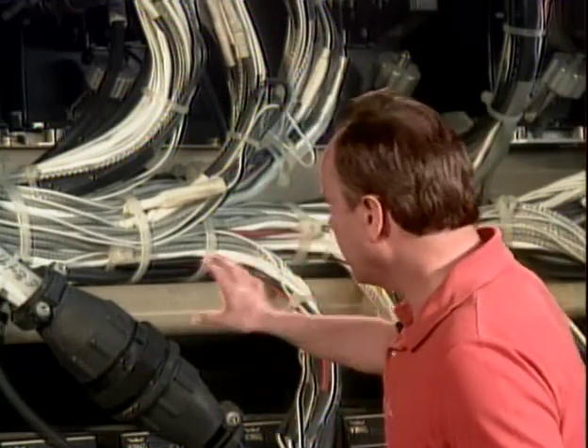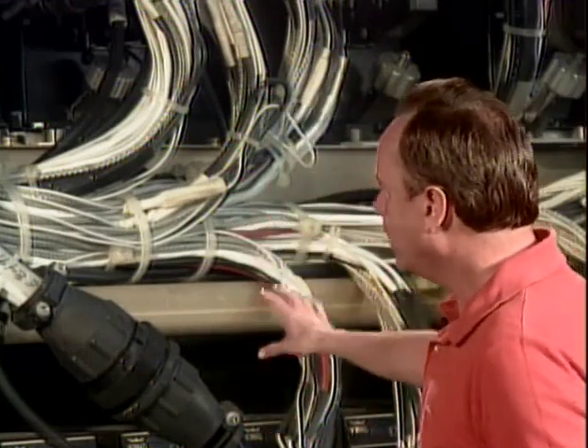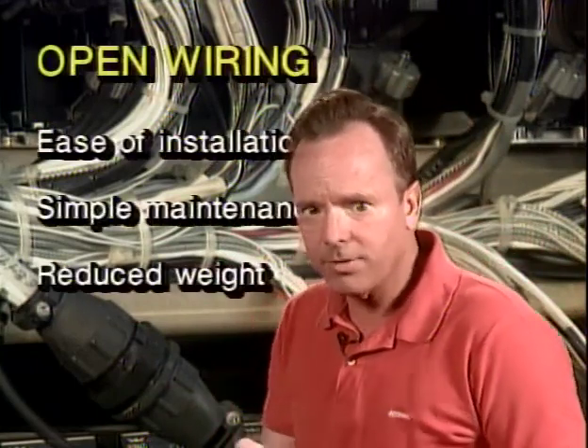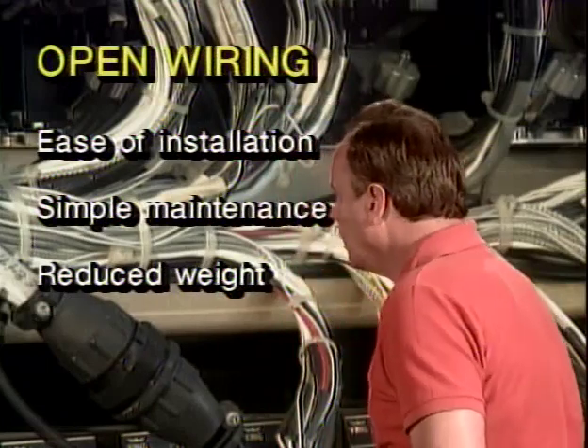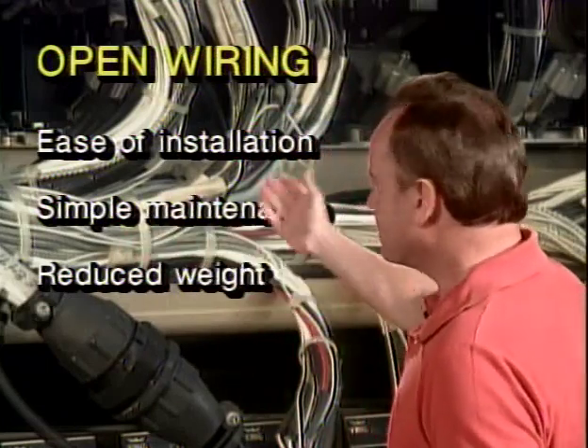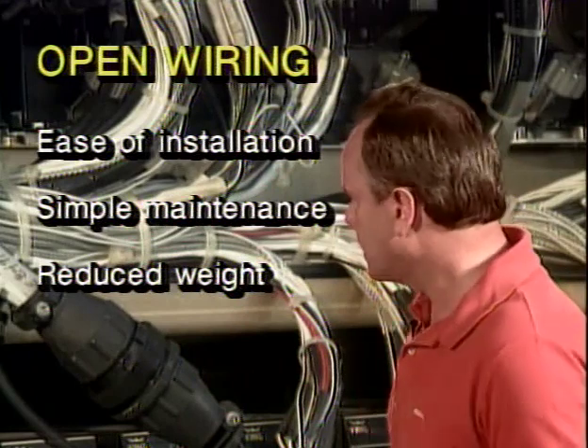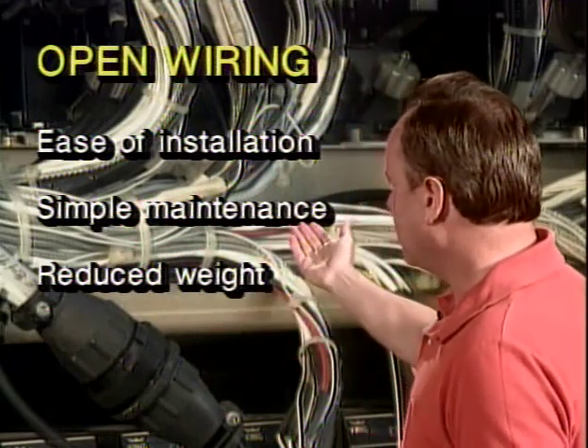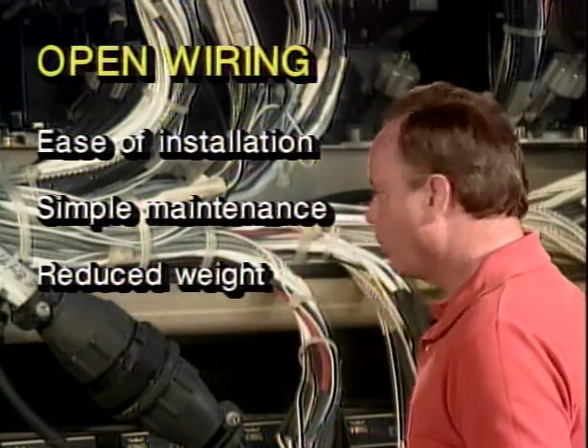Now, 2 ways you can make installations are with open wiring, or you can put wiring in conduit. Well, open wiring, that's wiring not in conduit, has some advantages. Let you and I take a look at the advantages the FAA wants you to know about for open wiring. First of all, ease of installation. You don't have to mess around with a conduit. That makes sense. Simple maintenance. You can get to it easily, and reduced weight. You don't have the weight of the conduit.